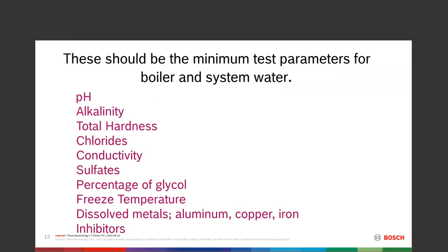A pH problem — whether alkaline or acidic — is eating the boiler and the system, including pumps. Chlorides are another extremely aggressive contaminant: sodium chloride, calcium chloride, that type of thing. A major cause of chloride contamination in well systems is road salt. Here in New Hampshire the state has a program — if your well is contaminated by road salt from state roads, they'll actually drill a new well for you. These chlorides eat aluminum, stainless, and all the materials used in heating systems.